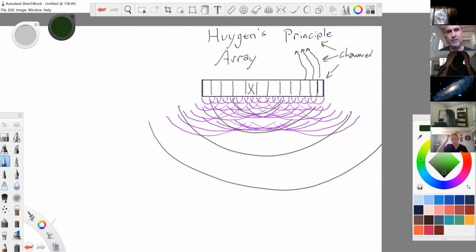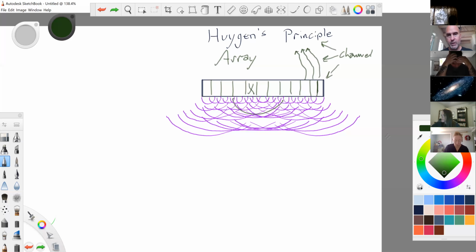It's not even a beam, it's just sound that spreads out in every direction. That wouldn't do us any good. So we use multiple elements at or almost at the same exact time. There could be very small changes in when exactly each one of these is stimulated, but that's steering, and that's focusing as well.